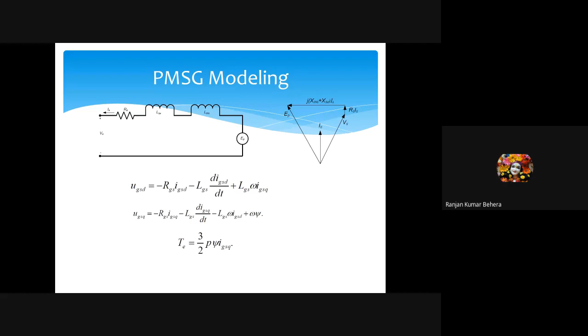So when we simulated, you can see here, these results are very, very important analysis to understand the performance. First thing is, when you connect to the grid, the grid side converter must operate utility friendly, so that the power you are feeding to the grid must be sinusoidal, and both the current and voltage must be at unity power factor, so that the reactive demand must be zero. So you may ask, there is some magnetizing component because of the winding or something. How is that handled? The small capacitor in the DC link can supply that very negligible amount in the case of multi-megawatt machines.